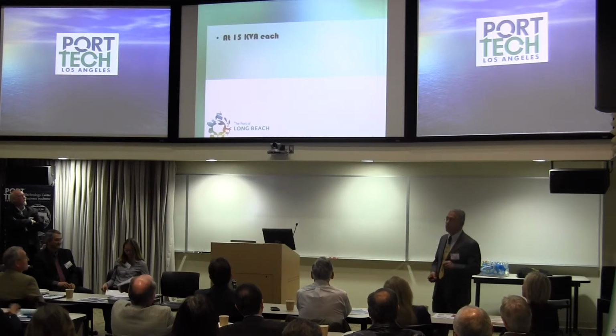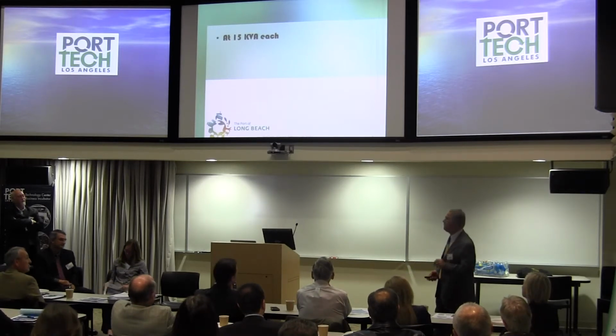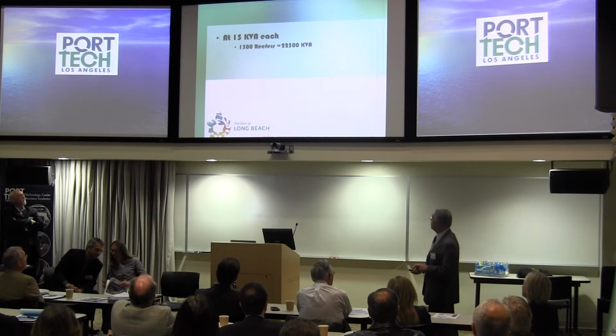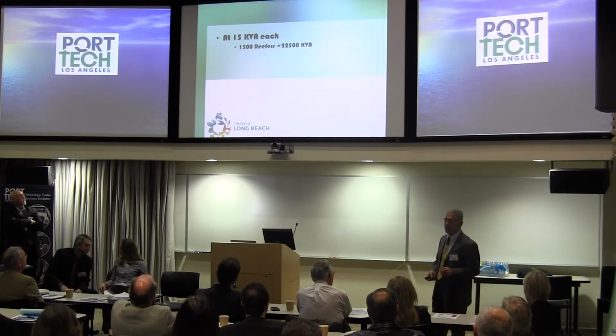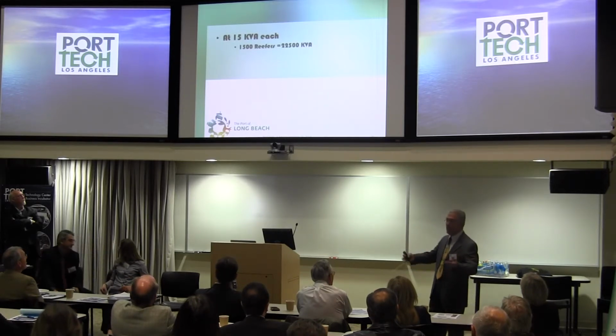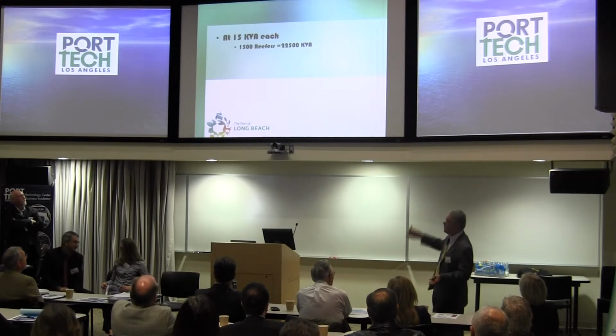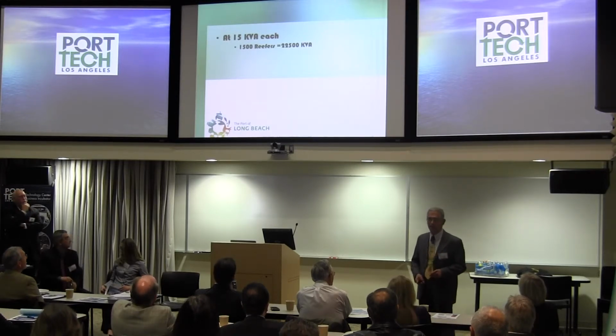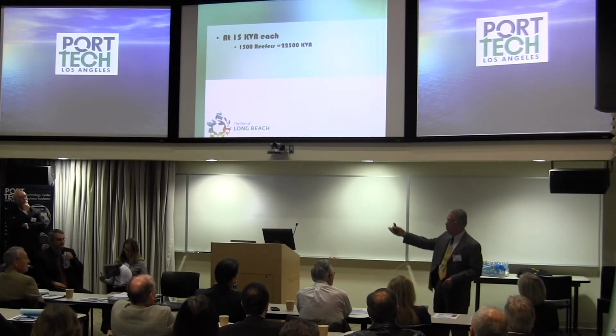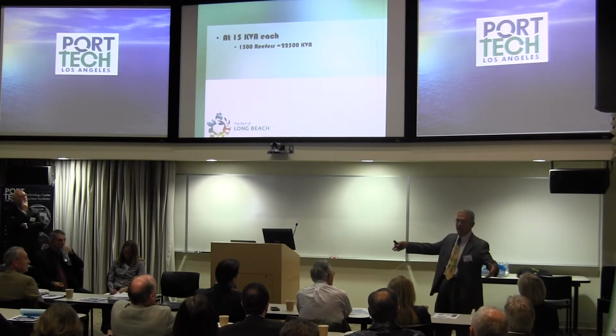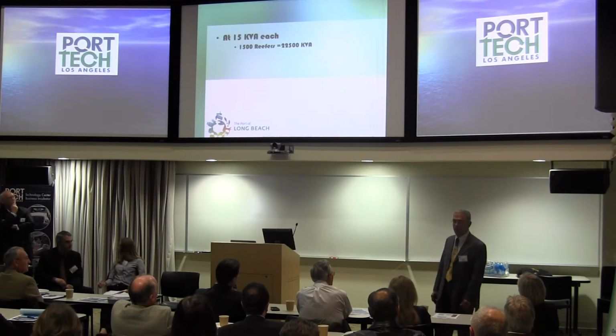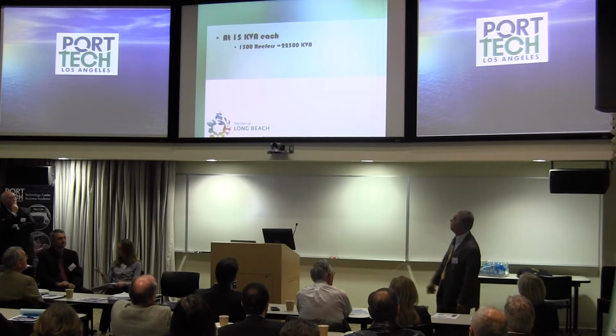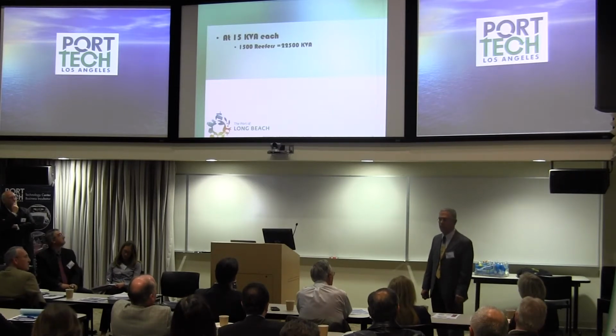Okay, what is the significance? Let's take a look at it. At 15 kVA, we decided we're going to have 1,500 reefers. Not a big math. You just multiply the two numbers and it comes up to 22,500 kVA. What Vahik was saying, you need 90 MVA and 90 megawatt and all that for the terminal, that's where it starts from. You need 22,500 kVA.